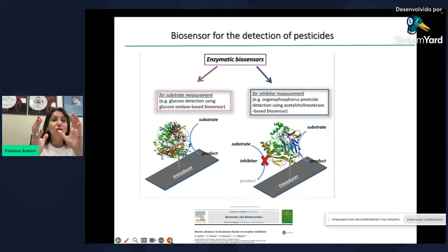This type of inhibition biosensor, for example, is used for detection of organophosphorus and carbamate pesticides, which are inhibitors of the cholinesterase enzyme. So our idea is to create a device ready to use without the addition of reagents, but only distilled water and the sample, for detection of this type of inhibitor. As said before, when we add the sample or distilled water, we have the dissolution of the reagents, because in this case we need to make the measurement in absence and presence of the inhibitor. We have to make two measurements. So how to manage this point?